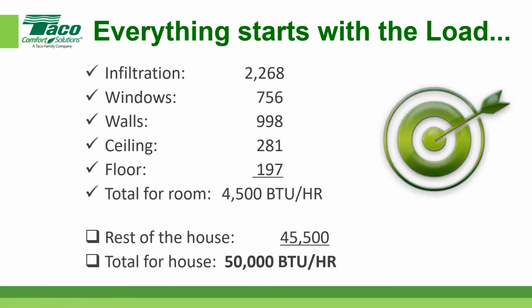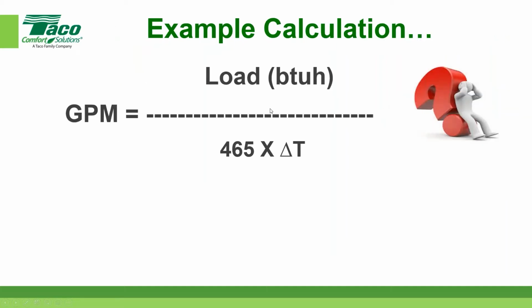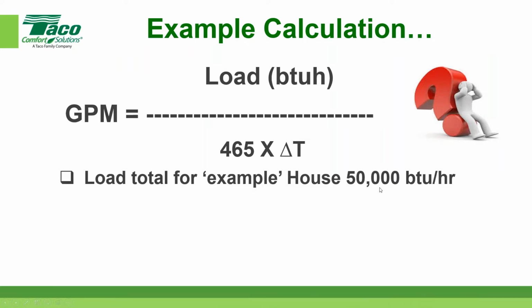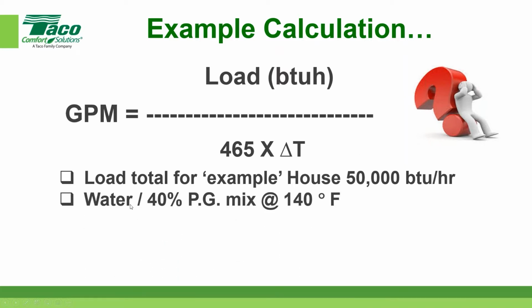So since everything starts with a load, let's go back to this. 50,000 BTUs. We're going back to what our target was, and let's do the calculation so you can put all the blanks in here. So our example was 50,000. 50,000 is going to go up here. We used water, 40% propylene glycol at 140 degrees. That's where we got this 465.